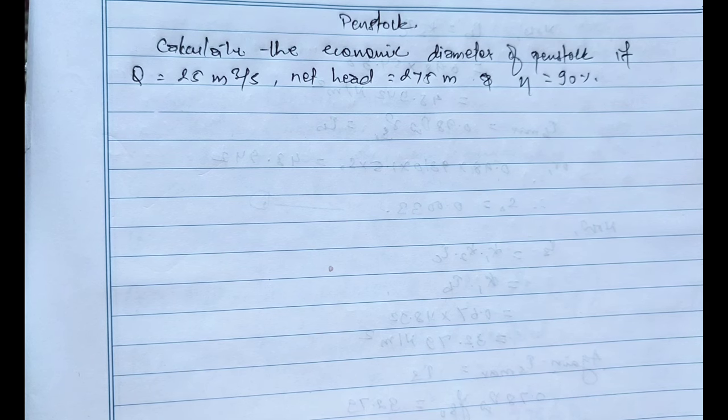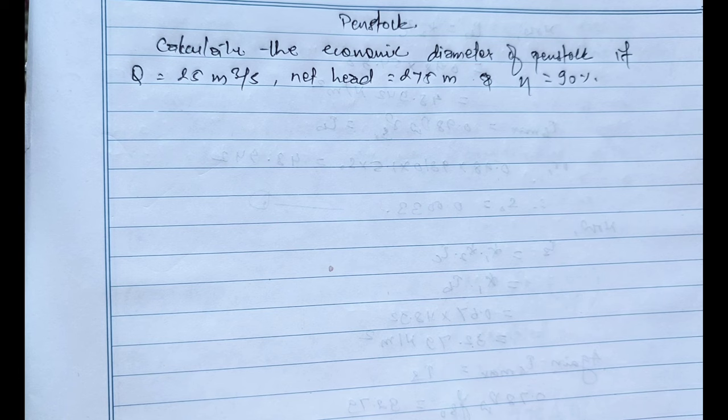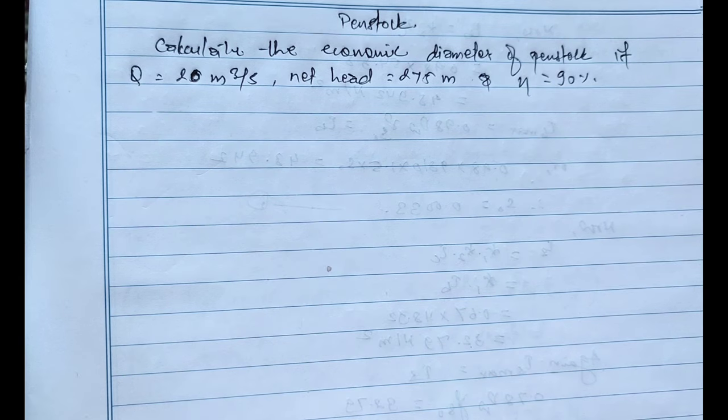Hello everyone, welcome to Hydropower. Today in this video we are going to calculate the penstock diameter. The given question is: calculate the economic diameter of penstock if design discharge Q is equal to 20 meter cube per second and net head equals 275 meters, where the efficiency overall efficiency is equals to 90%.